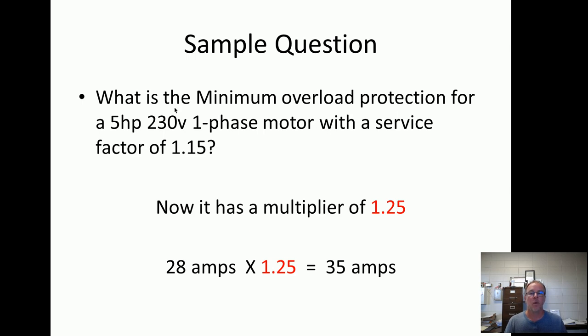What is the minimum overload protection for a single-phase, five-horsepower, 230-volt motor with a service factor of 1.15? It has service factor in there, so our multiplier is 125% (1.25). Our answer is 35 amps because we applied the service factor multiplier.